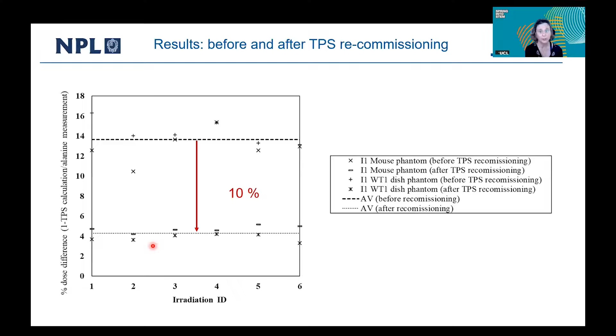One of the most important results was that the end-to-end test demonstrated that errors in the TPS commissioning files could be spotted. See here, a 14% difference between calculated and measured dose at institution number 1. After we saw that result, we had a conversation with the manufacturer and they recommissioned the machine. When we repeated the end-to-end test, the difference between the calculated and measured dose went down by 10%. So they are now at the level of 4%. That was a very good result to see that we can spot errors in the commissioning process in this case.